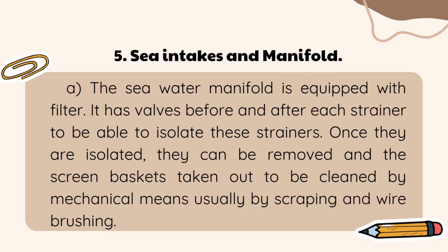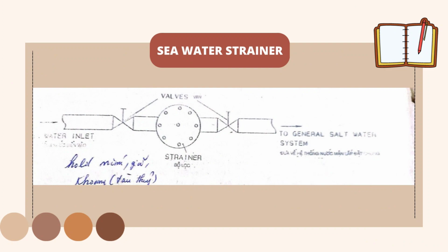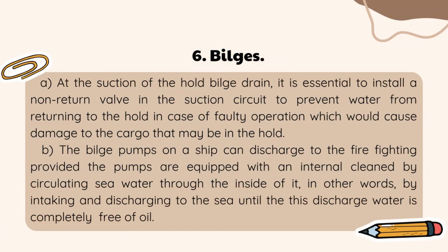5. Sea intakes and manifold. A. The seawater manifold is equipped with filters. It has valves before and after each strainer to be able to isolate these strainers. Once they are isolated, they can be removed and the screen baskets taken out to be cleaned by mechanical means, usually by scraping and wire brushing. Seawater strainer.